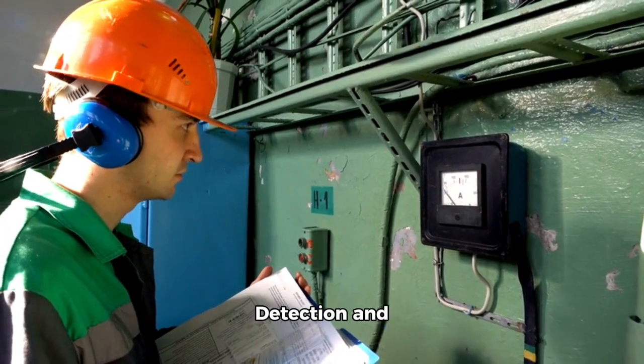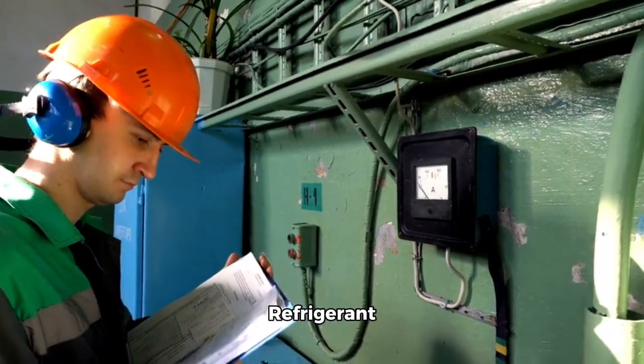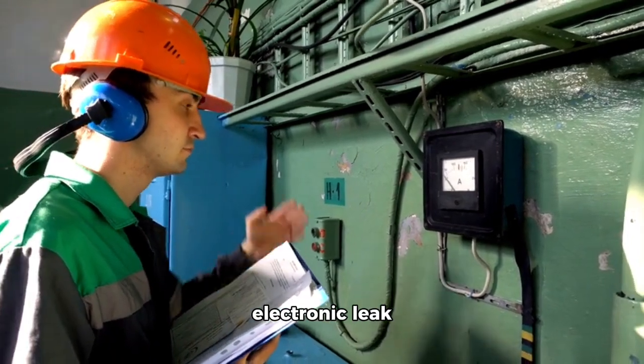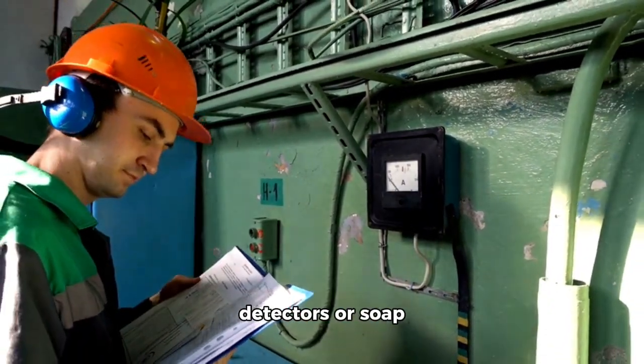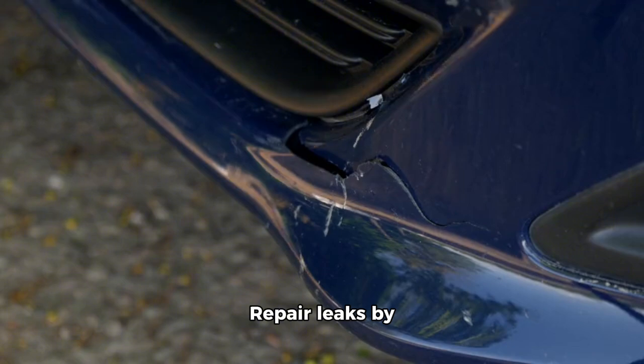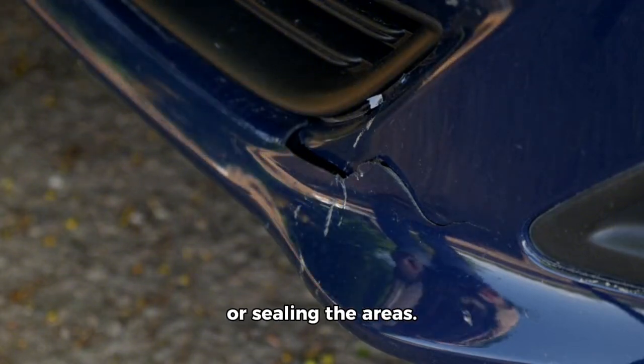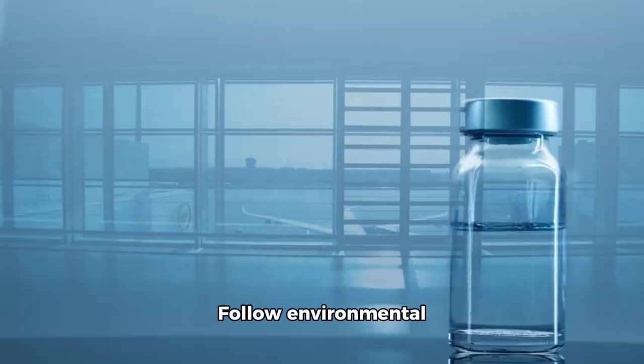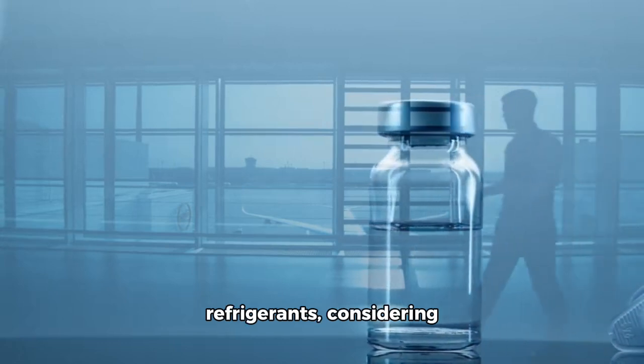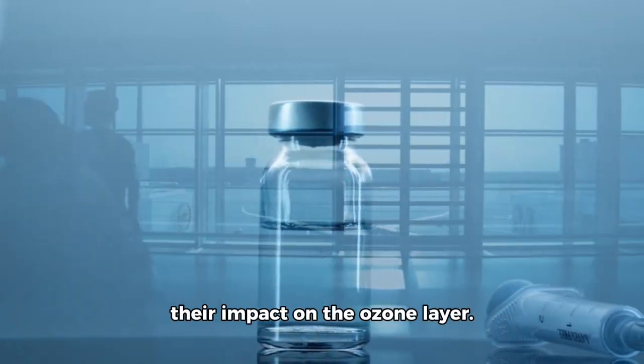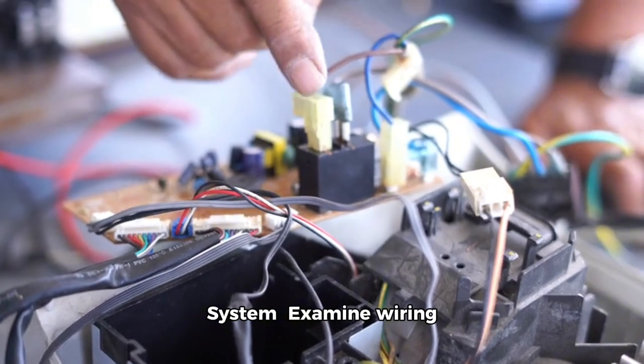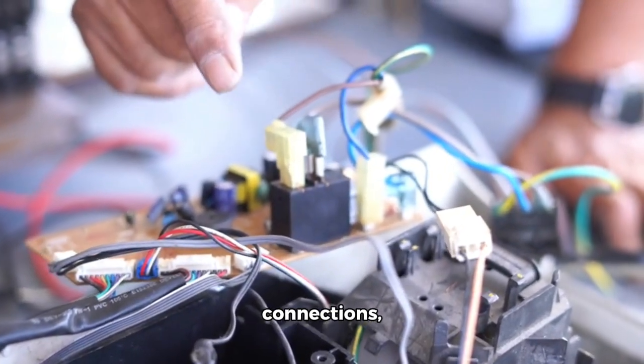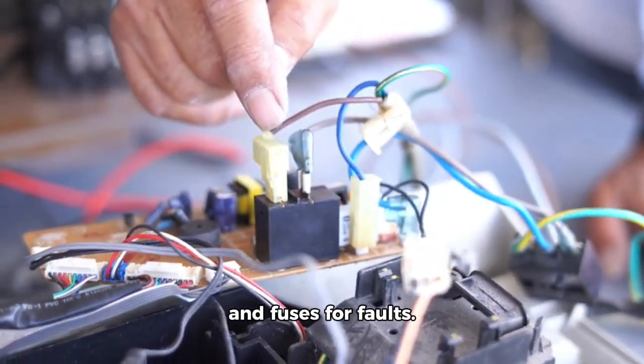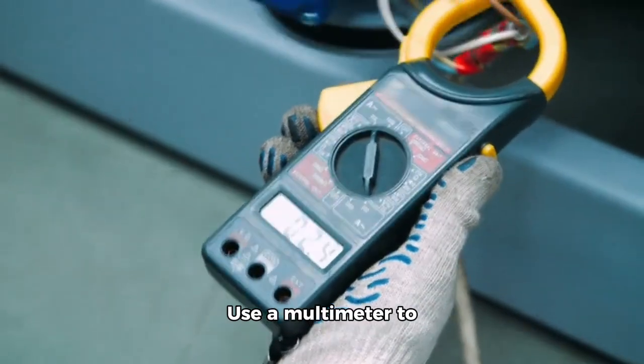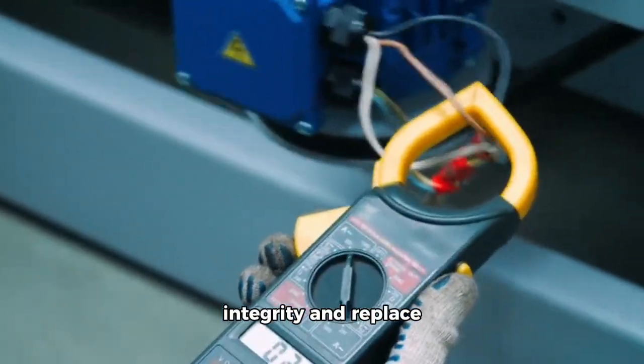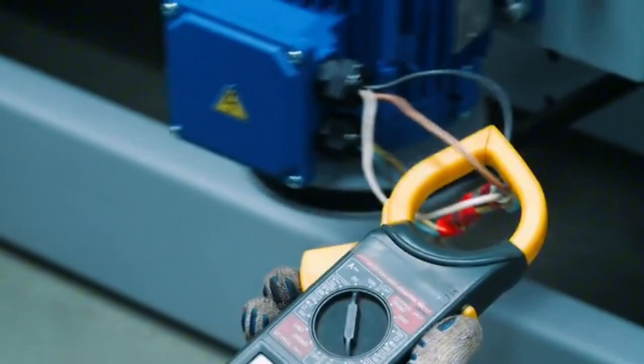Step 4. Leak detection and refrigerant management. Use electronic leak detectors or soap bubble solutions to find refrigerant leaks. Repair leaks by replacing faulty parts or sealing the areas. Follow environmental regulations when handling refrigerants, considering their impact on the ozone layer. Step 5. Electrical system. Examine wiring connections, capacitors, relays, and fuses for faults. Use a multimeter to verify electrical integrity and replace any defective components.